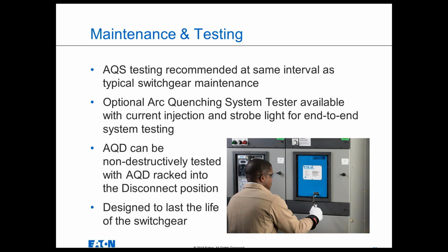And that verifies that the Arc Quenching device itself is operating. It'll non-destructively do a test fire to verify that everything's working. And then obviously when you flash all the sensors, it just verifies that they're all connected. Now, that being said, if a sensor does lose connectivity during normal operation of the switchgear, the relay will notify you. If the Arc Quenching device loses connection to the relay, or the trigger ribbons go bad, or the capacitor fails, anything goes wrong with the Arc Quenching device, you'll also be notified locally via LED light, remotely via Modbus.